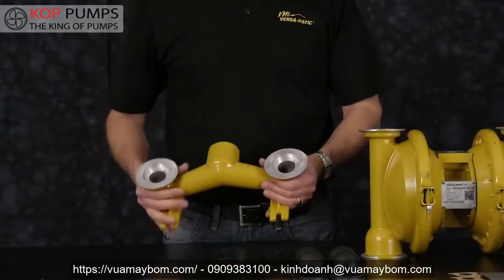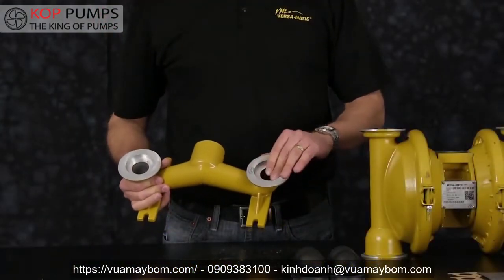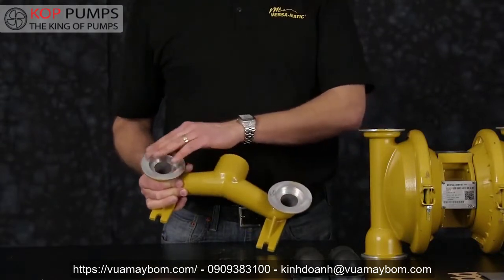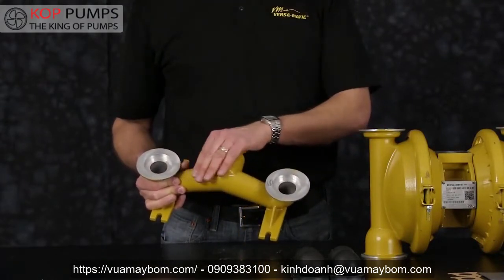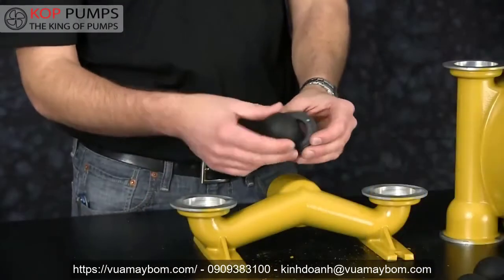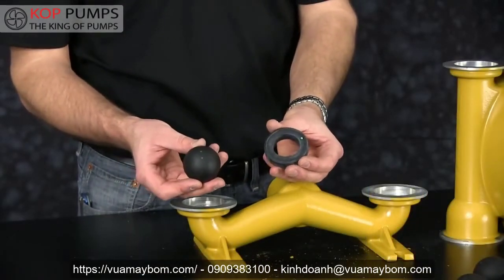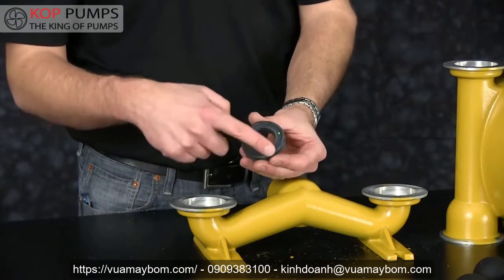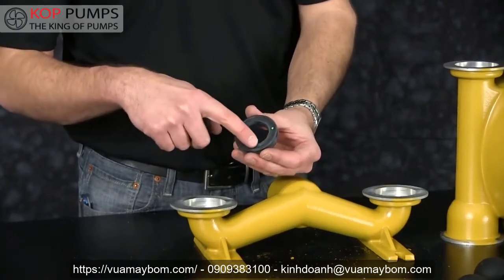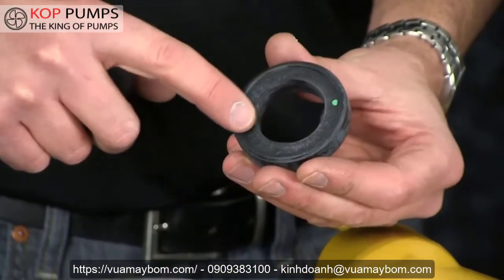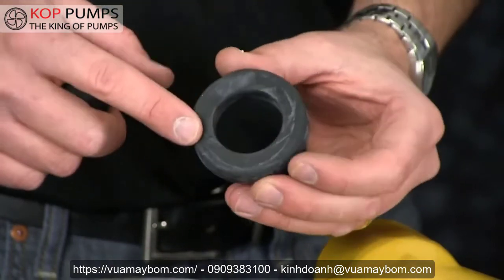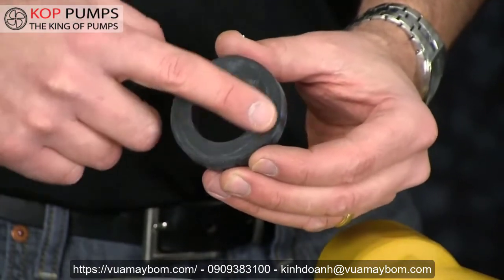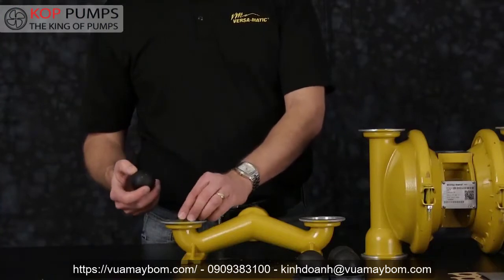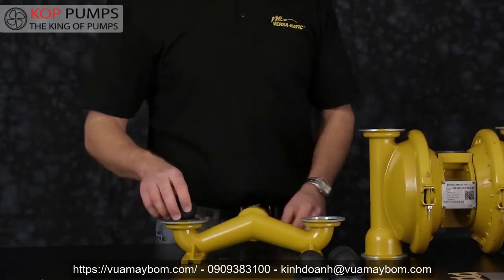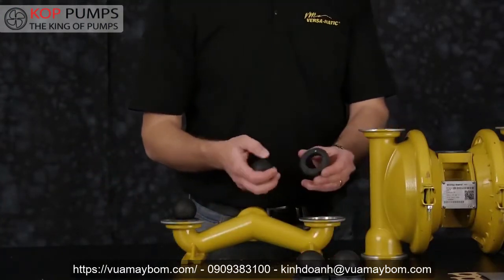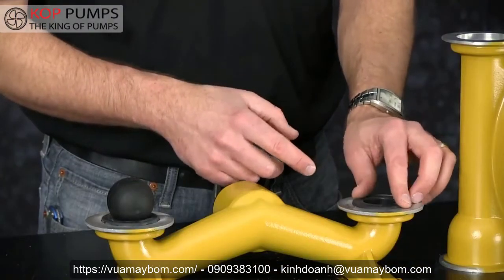Now we're ready to install our suction manifold. Inspect the integrity of the casting. Now we're ready to install our valve seat and check ball. We have the O-ring that's built into the check valve. We have part numbers in the flat surface on the opposite side. The flat surface will go towards the check ball and the O-ring faces down. Repeat this process for the opposite valve seat.